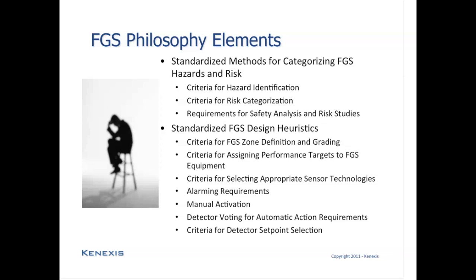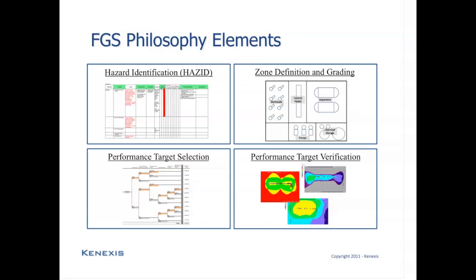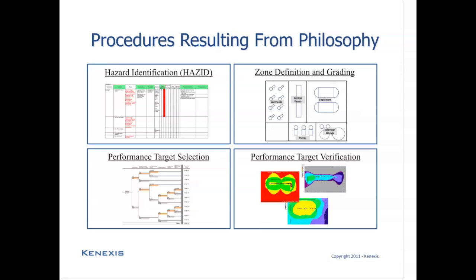There will be rules for how to vote various detection equipment, possibly in hopes of reducing nuisance alarms. And then there will also be criteria for selecting which set points are going to be used to activate alarms and to activate control actions based on fire and gas system detection. All of this information needs to be defined prior to going into the detailed implementation of any project. And again, this should be done at a higher level in the organization and then consistently applied across all equipment in all facilities.